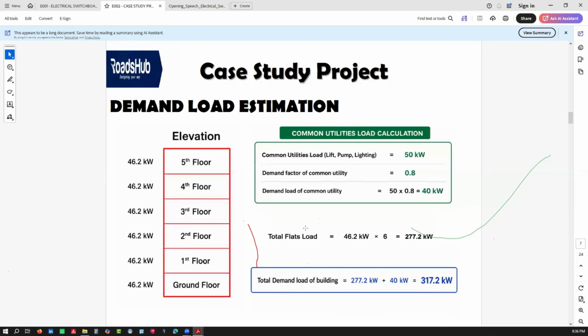You can follow the math at a later time to prove it yourself. But the point here is that when I'm doing load estimation, I use demand load. The reason is you don't want to incur a lot of expense, and the diversity factor explains to us that each load will not peak at the same time. Each load will not be connected all the time. Sometimes you're even out of your house and the load is at 0. So you wouldn't go with the exact load size without putting in a demand factor, because you will incur a lot of cost buying your items since the sizings will not be realistic. So for MEP engineers who do high-rise buildings, you understand that because this is what you do every day. Okay? But towards the end, you'll see the difference introducing this makes for us.